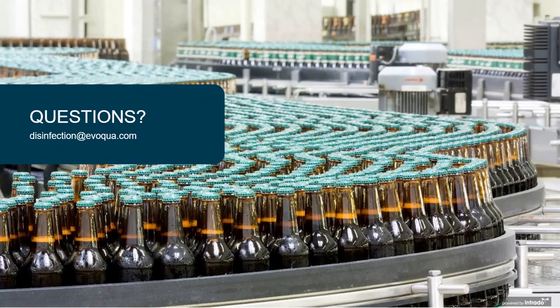So most of the manufacturers will give recommended periods. These devices are typically amperometric probes, and they do have an electrolyte in them that will fade over time, and the membranes will oxidize over time. So typically, it's not uncommon to see those things being maintained quarterly, semi-annually. So it's a very common practice.